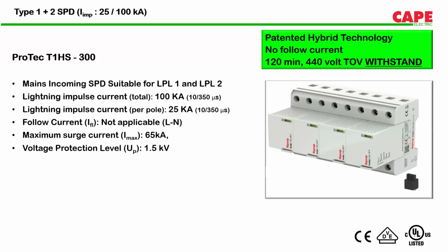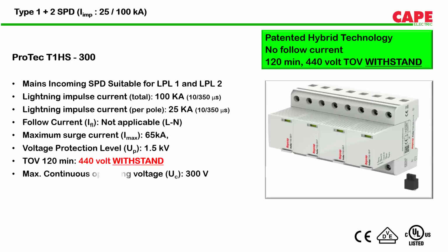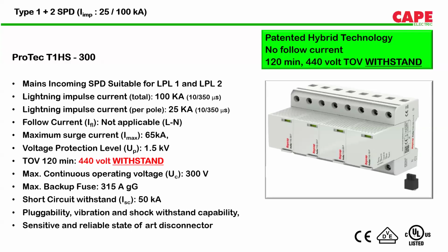It has a maximum discharge current of 65 kA per pole line to neutral and 130 kA neutral to earth. Again, one more advantage of these SPDs is that all of these SPDs are pluggable in nature. What do you mean by pluggability? So if you see, for each phase we have a separate plug.